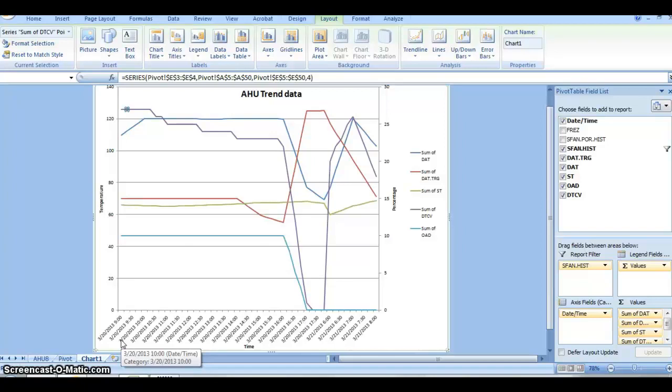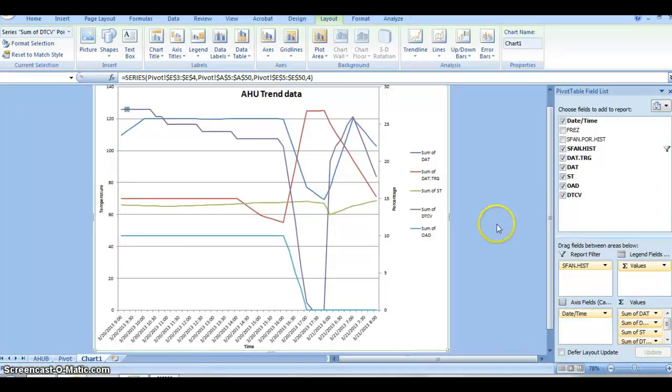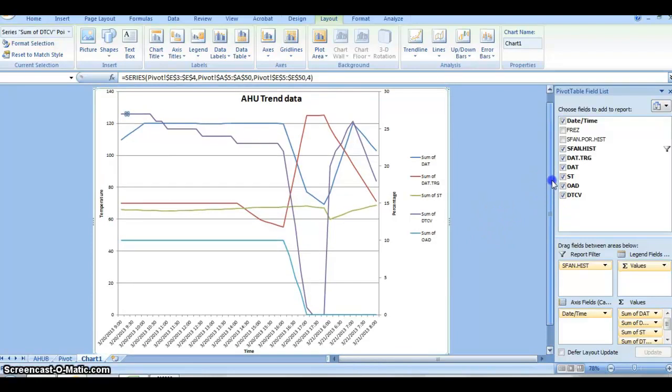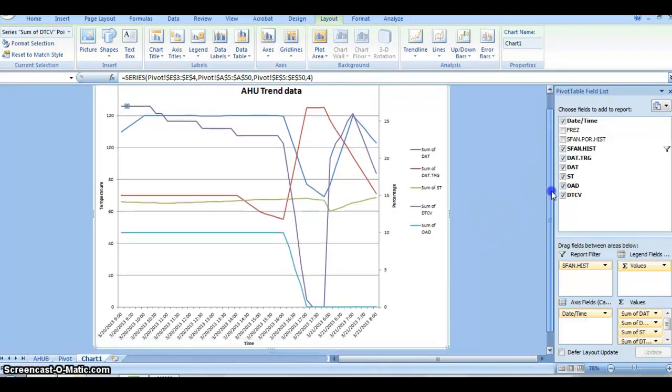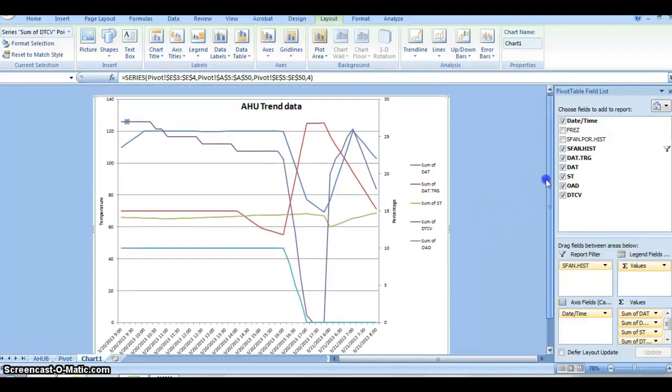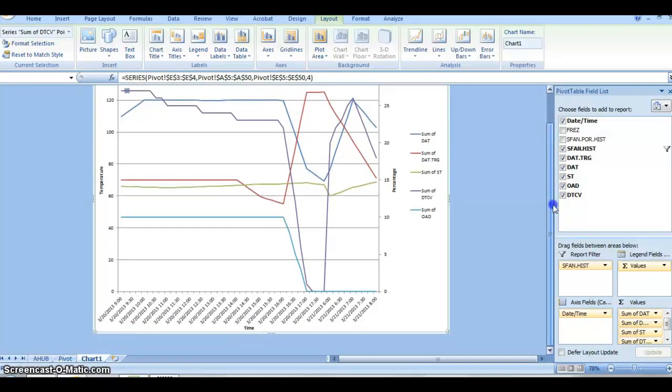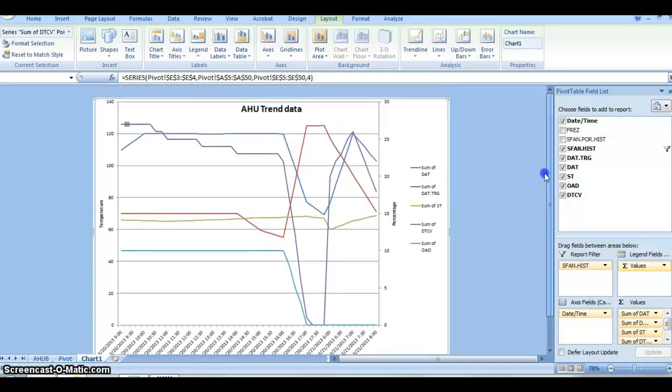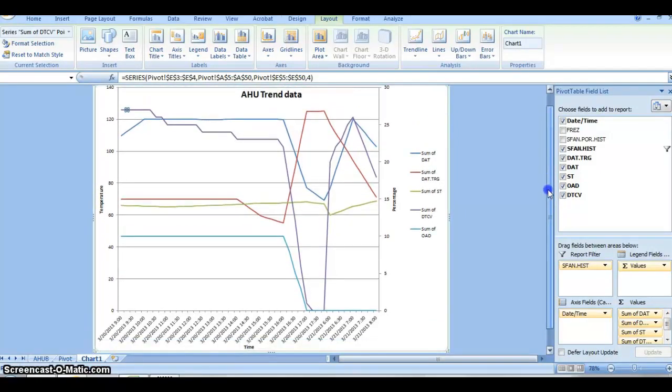You just look for logical errors in the system when the supply fan shouldn't be running. You know, if the cooling valves are running during late nights, such as like midnight on a weekend, you look for logical errors. So that's how you trend data, and thank you for your time.